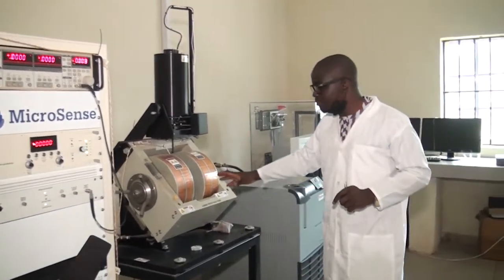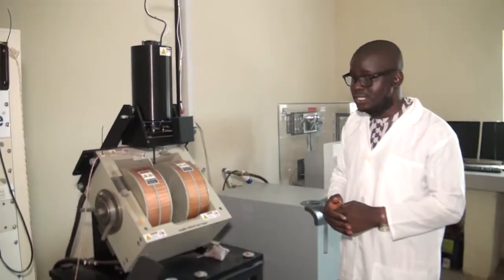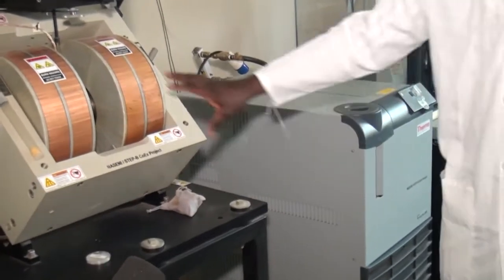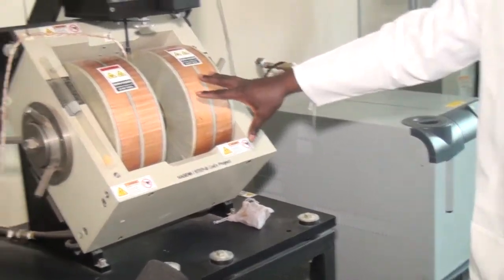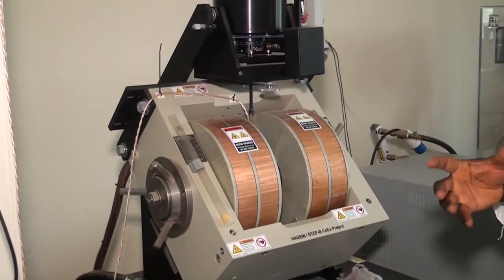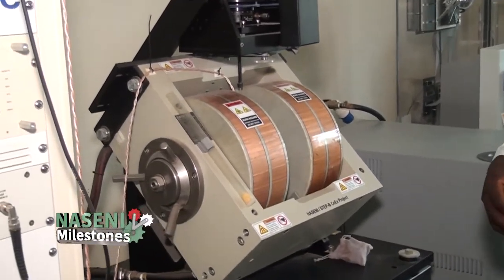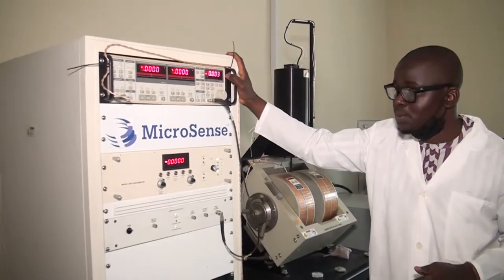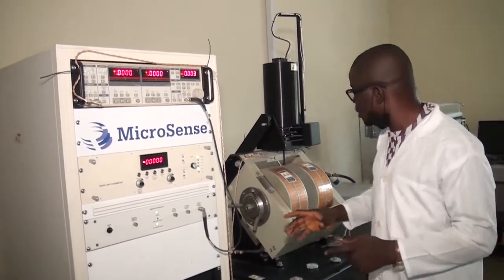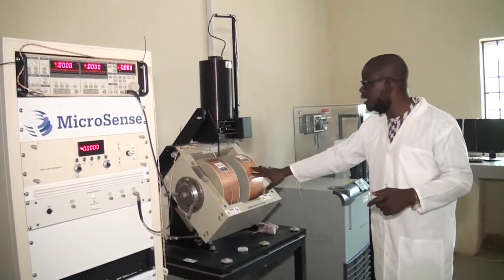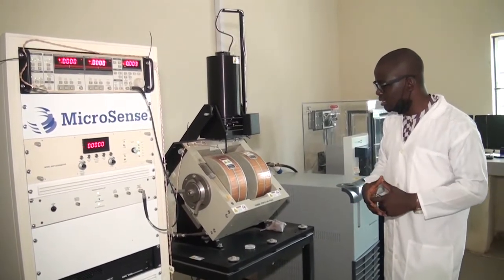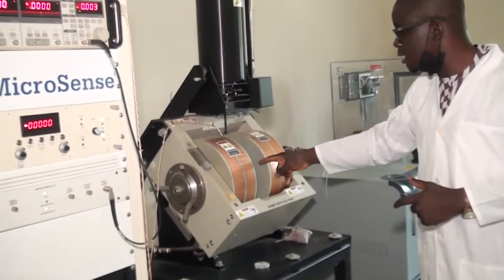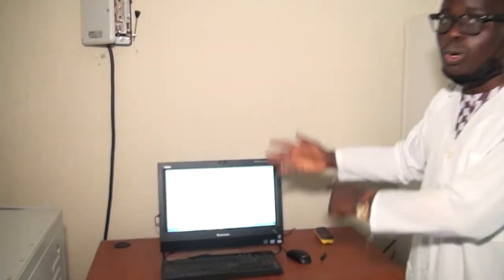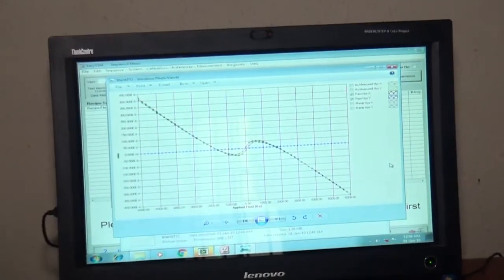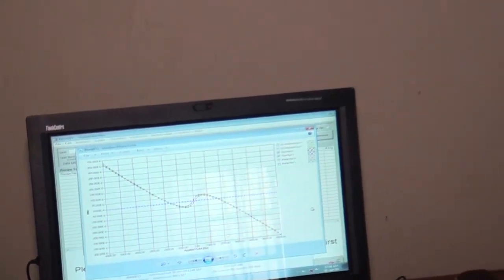Basically, the equipment has like three or four parts. We have the chiller here, which is used to cool the electromagnet when it gets hot during operation. Then we have the electromagnet here, which produces the magnetic field that we need to analyze the material. We also have the control system, which supplies appropriate power and voltages to the different components, including the electromagnet, the vibrator, and the magnetic moment sensor. We also have the computer system, which is used to control everything, because everything about the equipment is automated. A user just needs to prepare the sample, do the calibration, and then run the test.